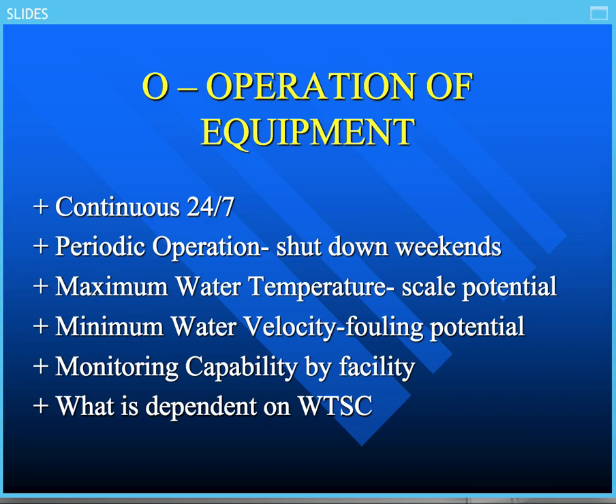It could cause deposition during that time. How it impacts your water treatment program is that it usually requires higher dosage levels during those periods of time. In fact, it's better to carry a higher dosage level when you do have periodic operation. What's a higher dosage level? 50 to 100% higher in many cases, particularly for deposit and microbiological control, but it could also be for corrosion control.